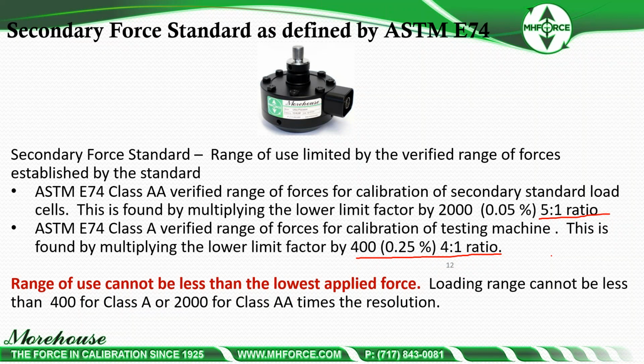Loading range cannot be less than 400 for Class A or 2,000 for Class AA times the resolution. So if I have a device with a 1-pound resolution and I want a Class AA loading range, the first point that I can take as a calibration at our facility is 2,000 pounds. I cannot take 0 as my first test point. It is not allowed.